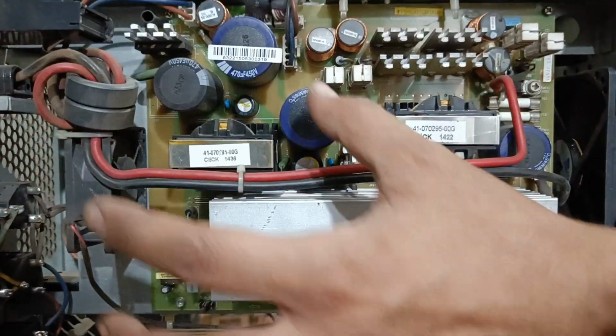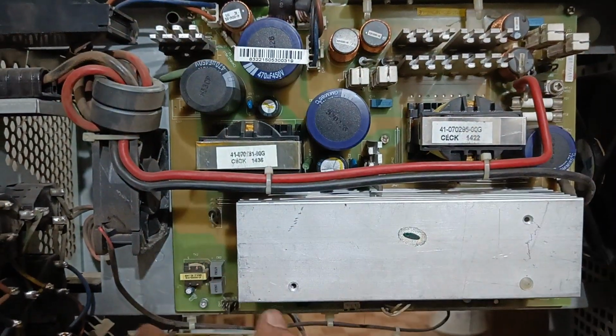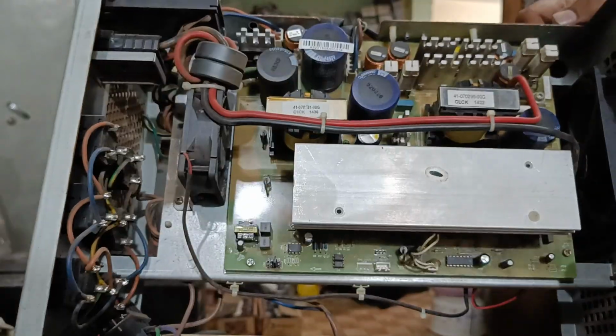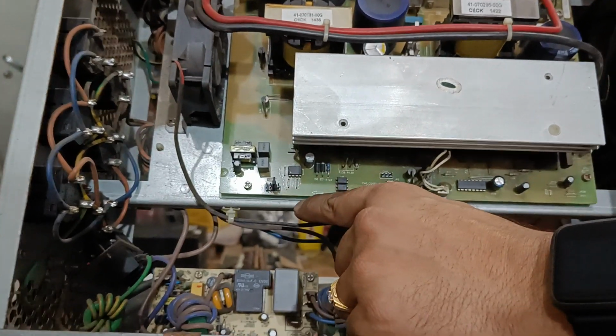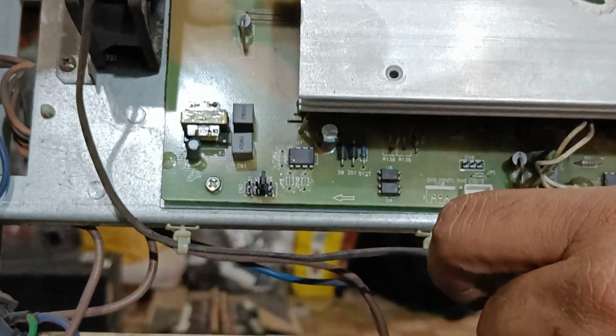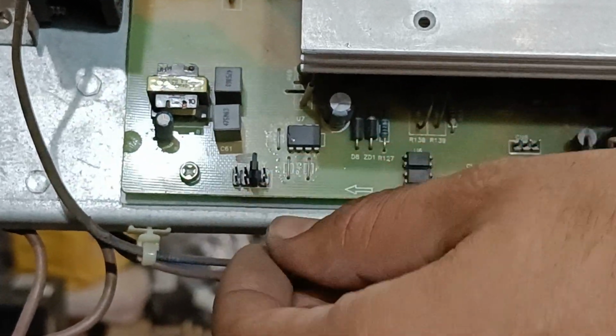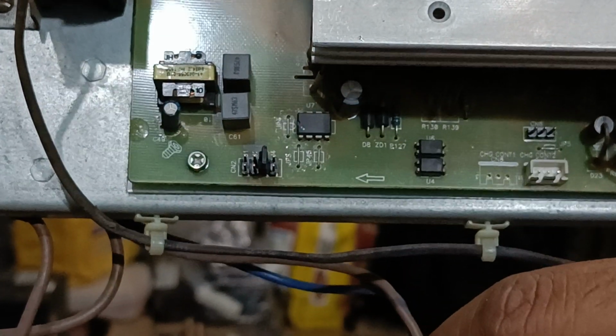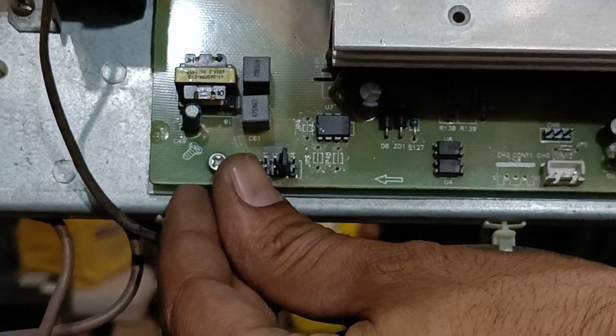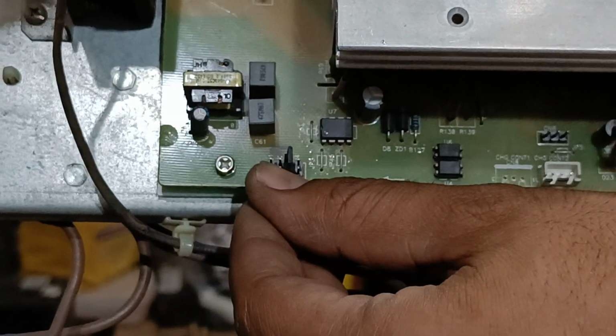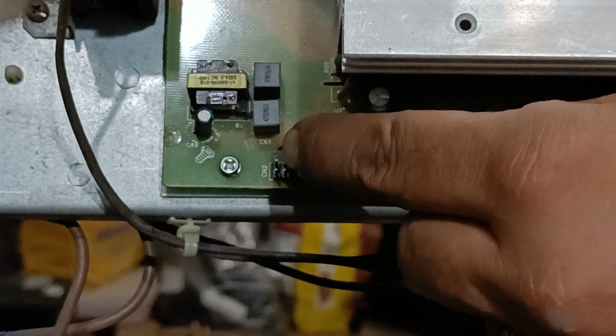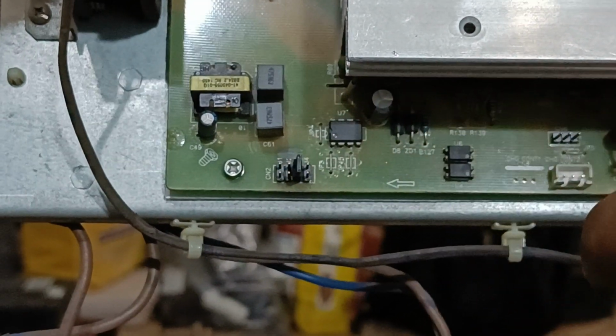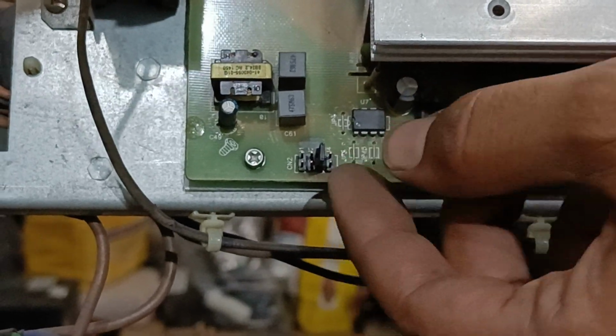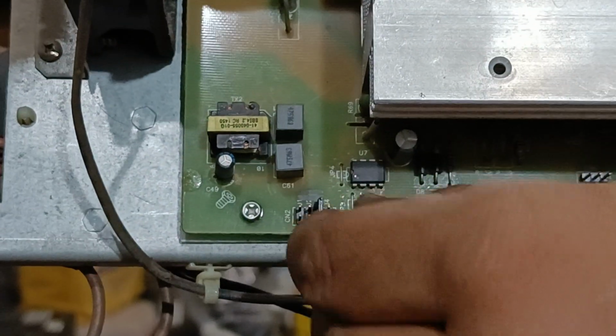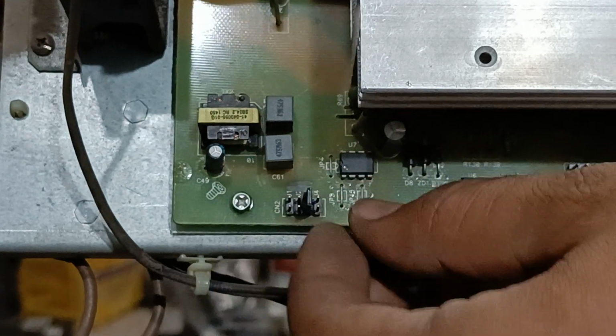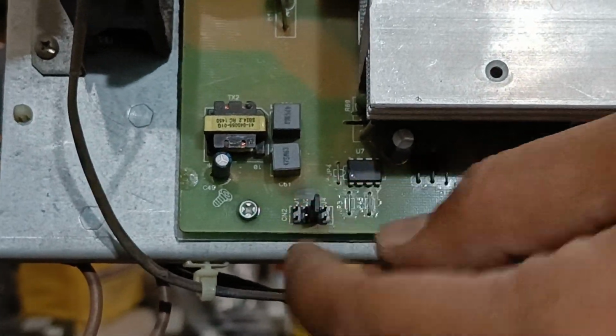So this is clear: this is the charger section, this is the booster section, and these are the settings. You get whatever ampere you want. If you have a 26 ampere battery, you can put the charging current to 2 ampere. The first setting is for 1 ampere, the second is for 2 ampere, right now it's on the third which is for 4 ampere, and at the end you get 6 ampere. So I suggest you put these jumpers on position 3, where you get 4 ampere.